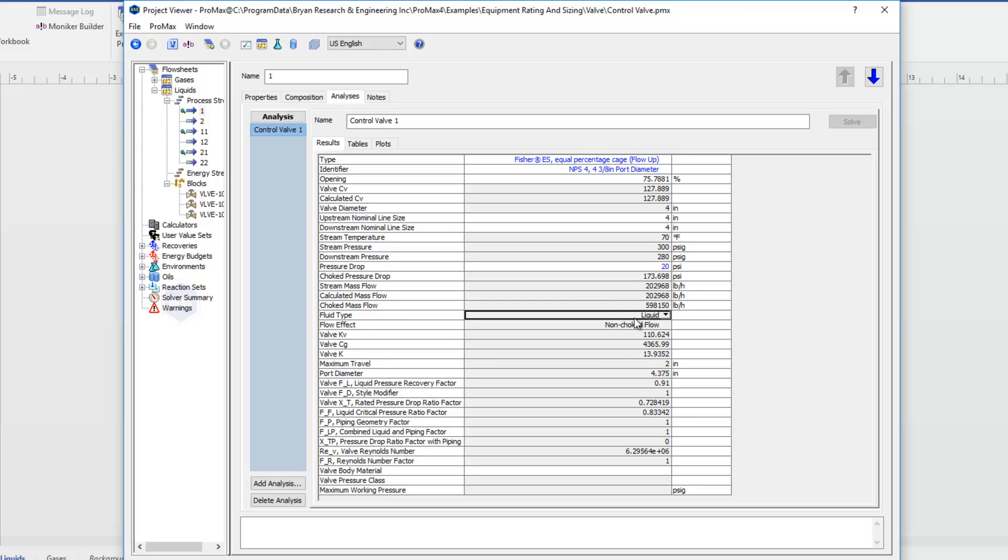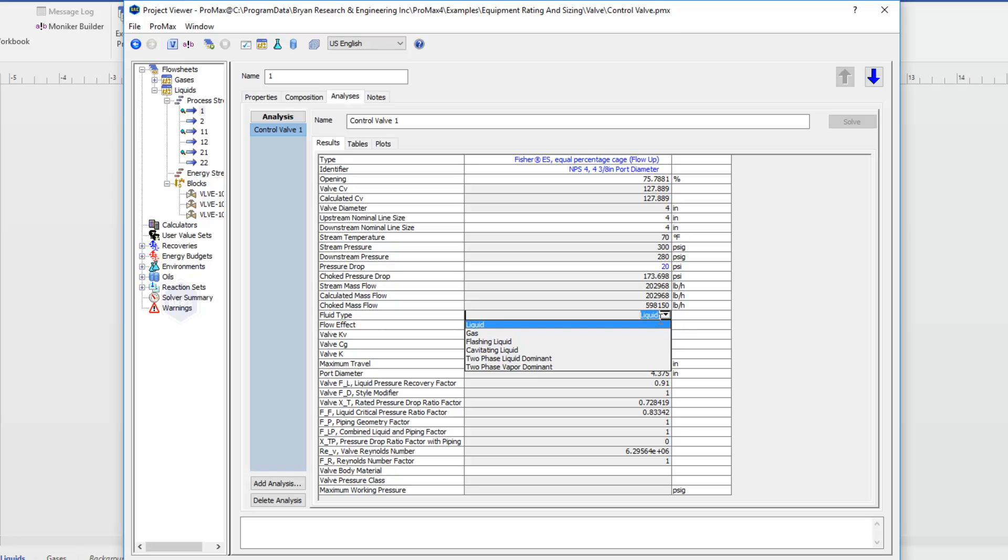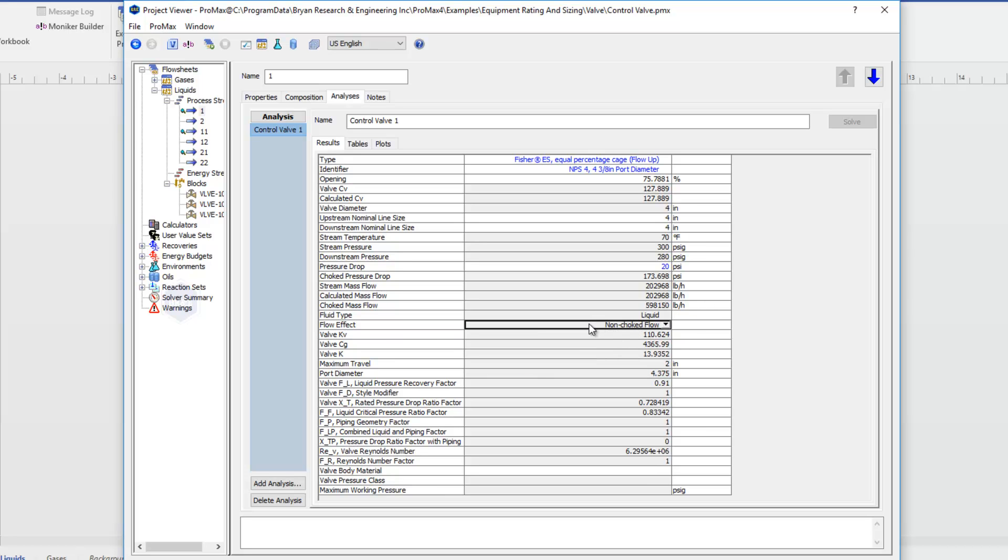Promax will tell us what type of fluid we have going through this control valve. Whether it's a liquid, a gas, a flashing liquid, two phases, etc. And it's going to tell us if we are in a non-choked flow or if we have choked flow.